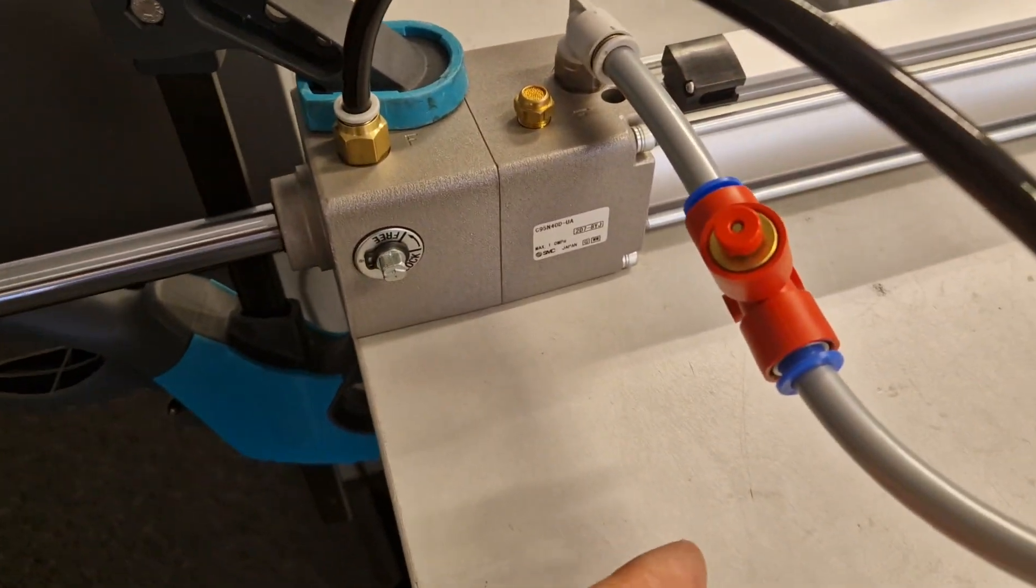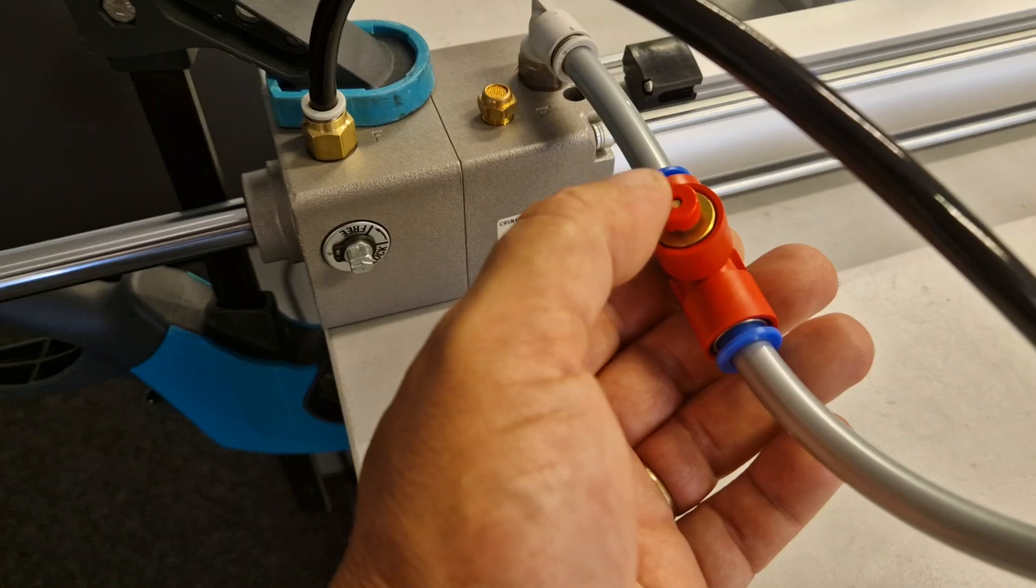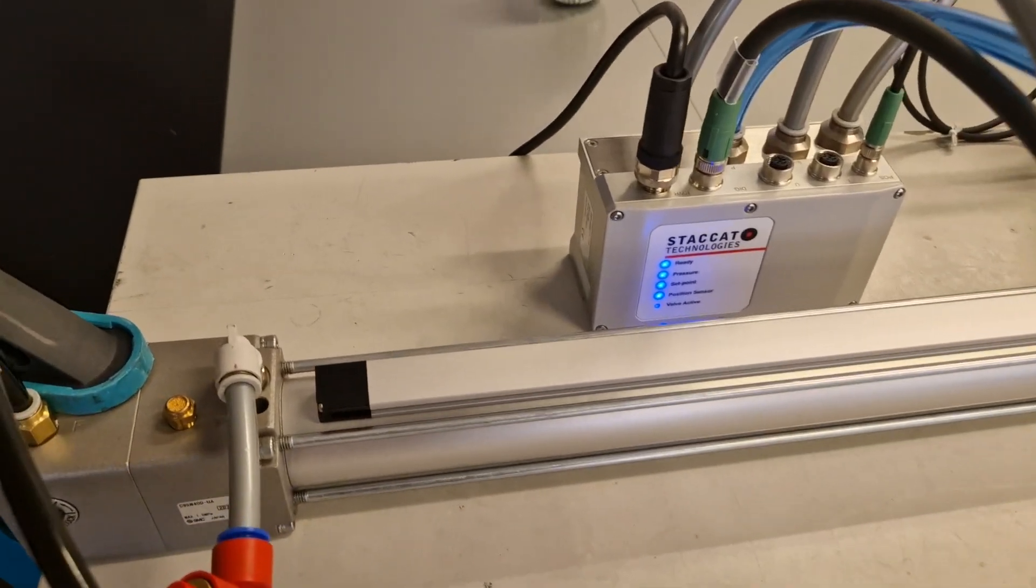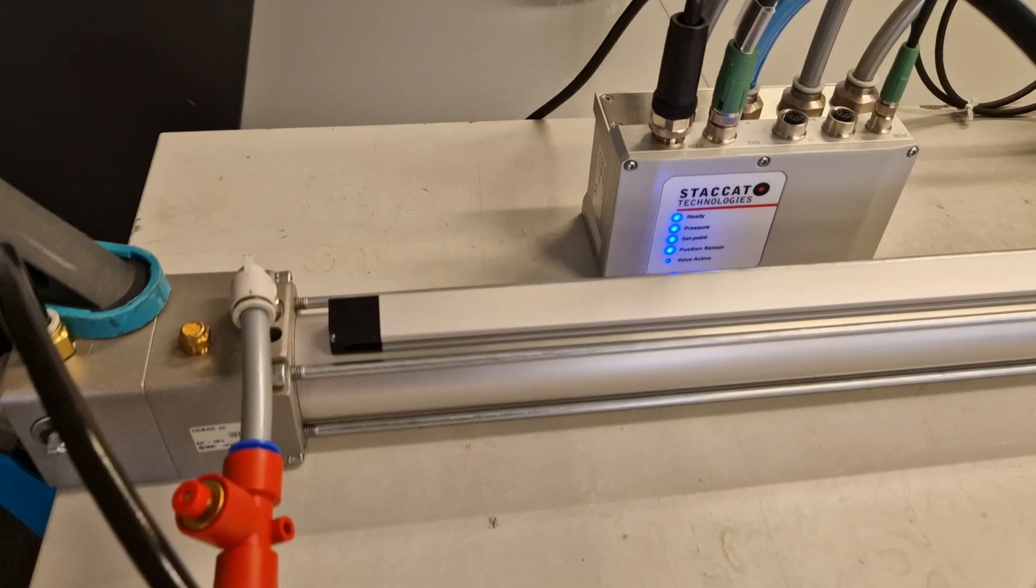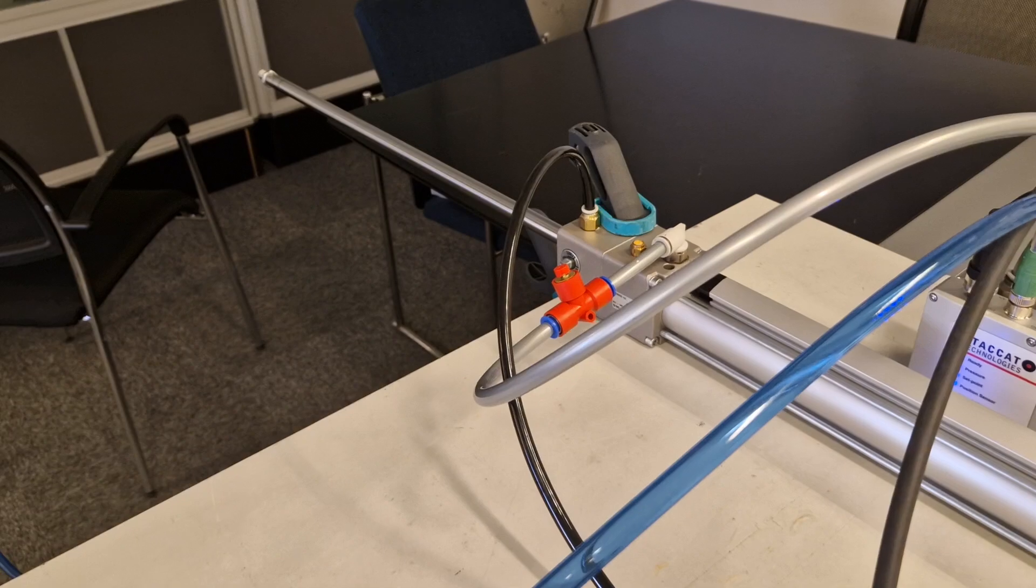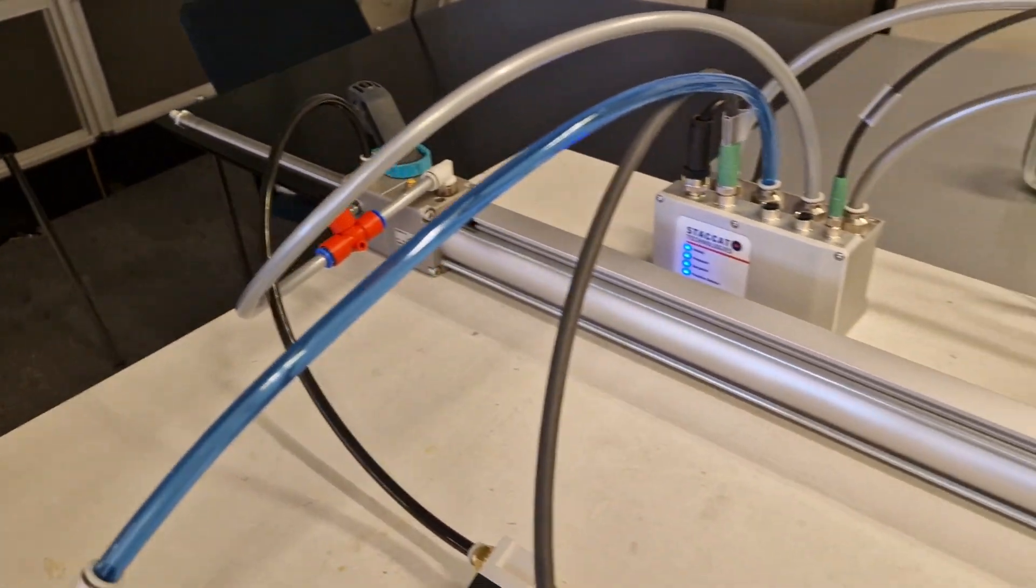It also monitors the pressures continuously. If you have a leakage, like here, you hear that the positioning unit compensates for the leakage, so we don't have dangerous movement when you start positioning again. Simple as that.